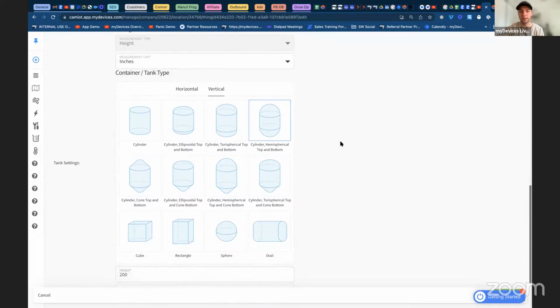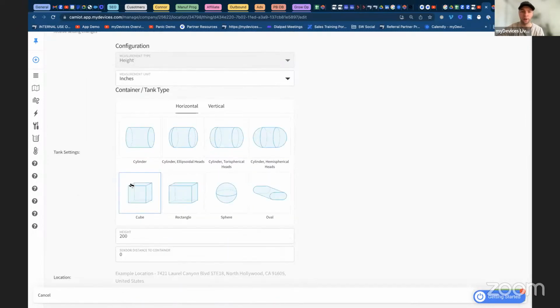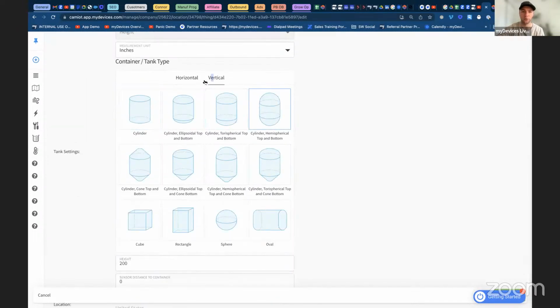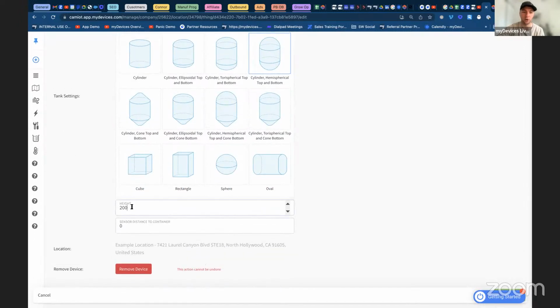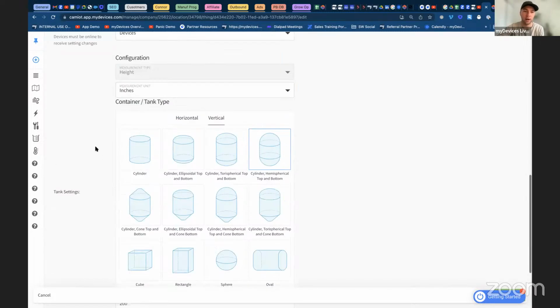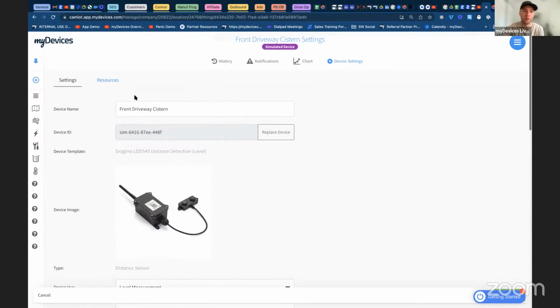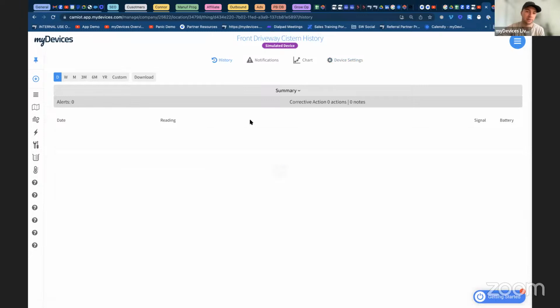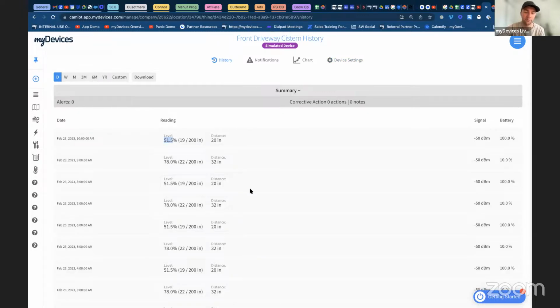What we do instead is collect user input: is it going on a horizontal tank or a vertical tank, how tall is the tank, what's the distance between the bottom of the sensor and the top of the tank. We need to eliminate that buffer from the equation because what the user really wants to know is how full the tank is. These parameters feed into the configuration so that when the data is resolved and shown, you get figures like 51.5% or 78%.